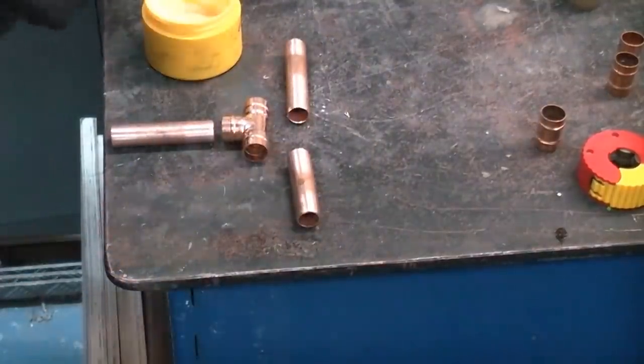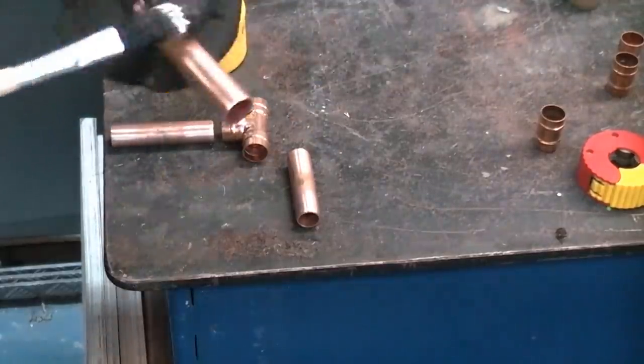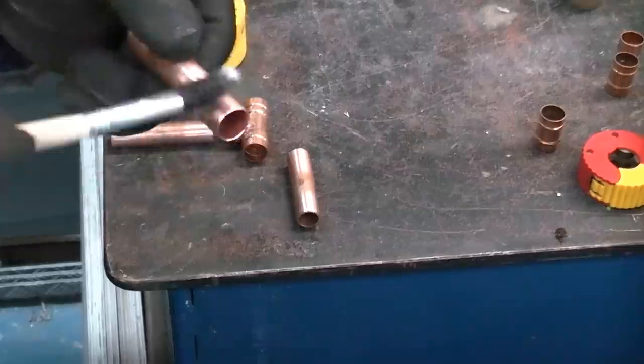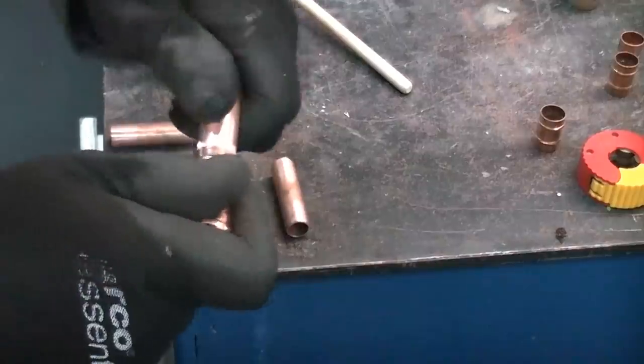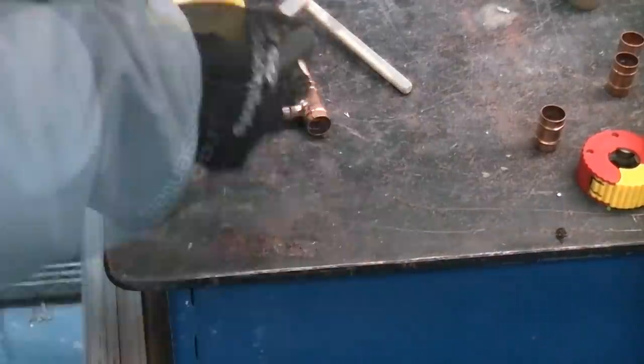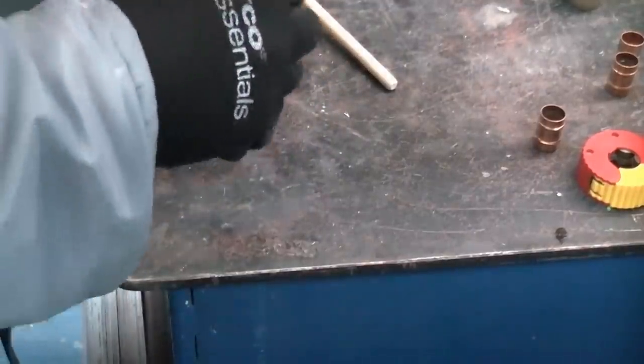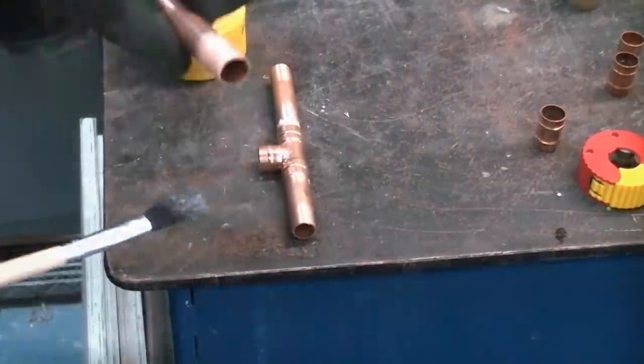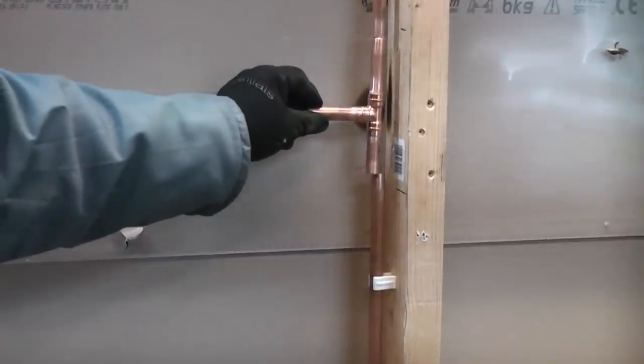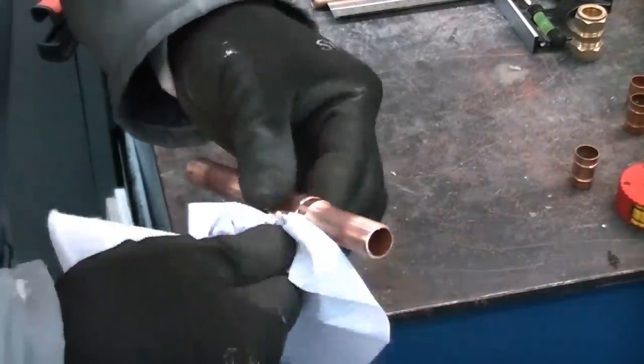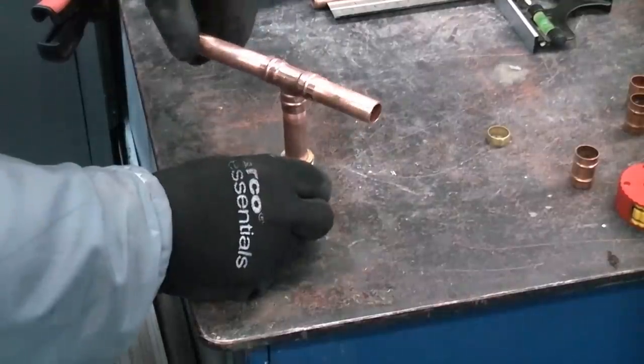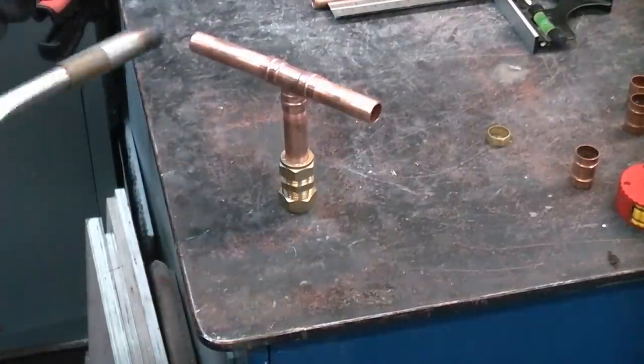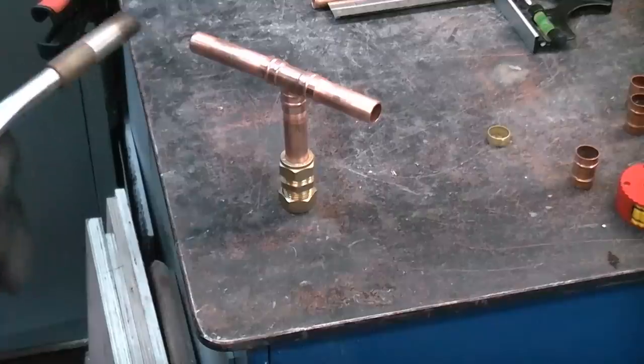I'm then going to take a flux brush and I'm going to apply some flux to each of the pieces of copper. Once we've done that we can then push that into the fitting. We can then just check we've got the pipes the correct way around before we solder it. I'm now just going to use a paper towel to wipe off any of the excess flux. I'm then just going to stand that up in a fitting just so that we can solder it. I'm now just going to apply some heat to that until the solder exits from the fitting.